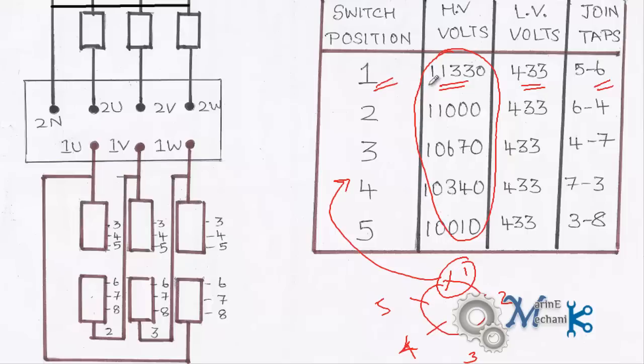At position 1 we have 11,330 volts. Position 2, we have 11,000. Position 3, we have 10,670. Position 4, 10,340. Position 5, 10,010 volts. However, what you have to note is on the LV side the voltage is constant, that is just 433 volts. There is no change in it. One more thing you have to note is the joint tap position. Let's say you want 11,330 volts on the primary side and you are choosing position number 1.